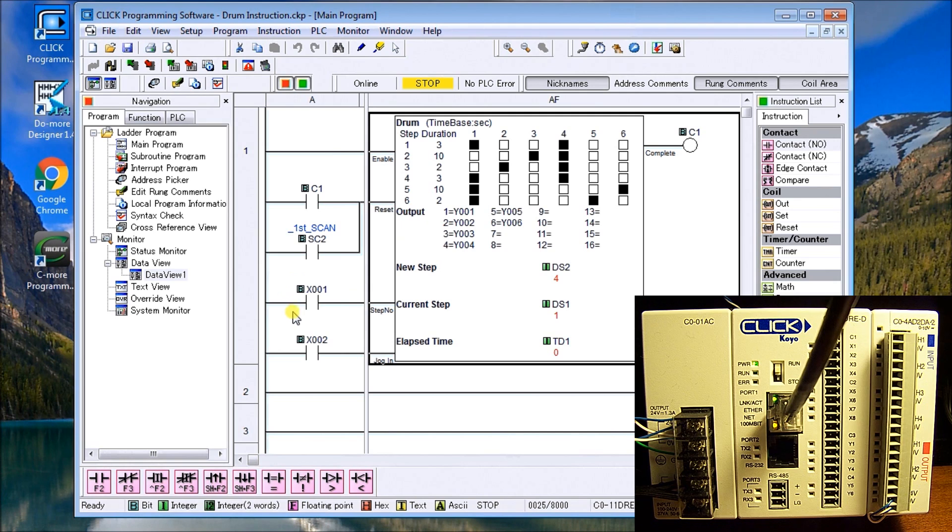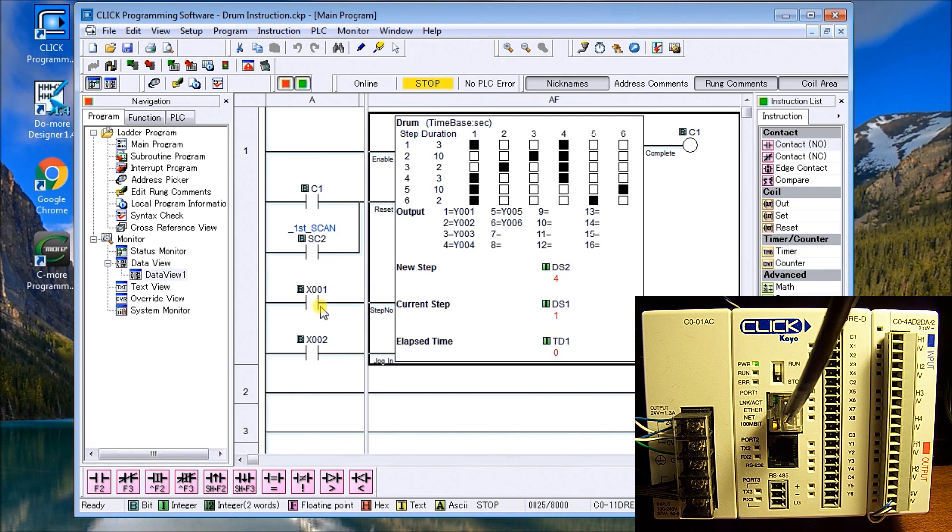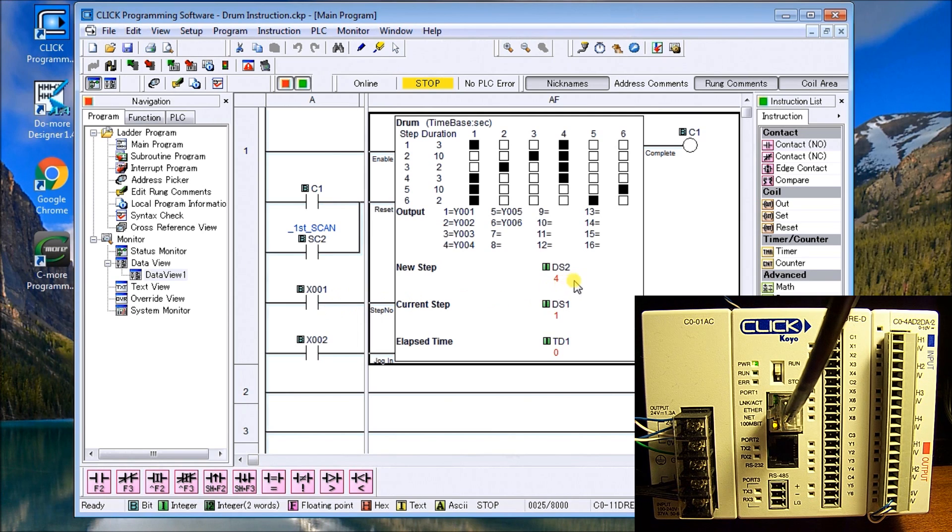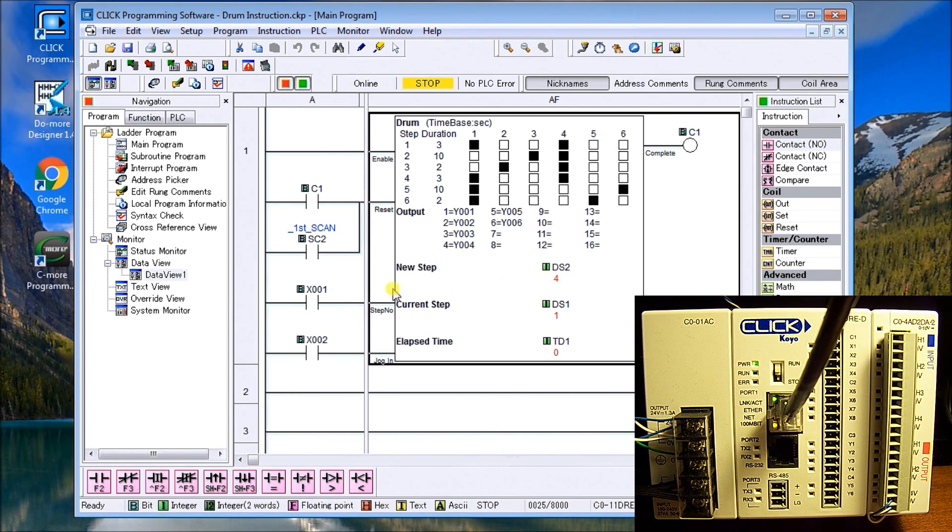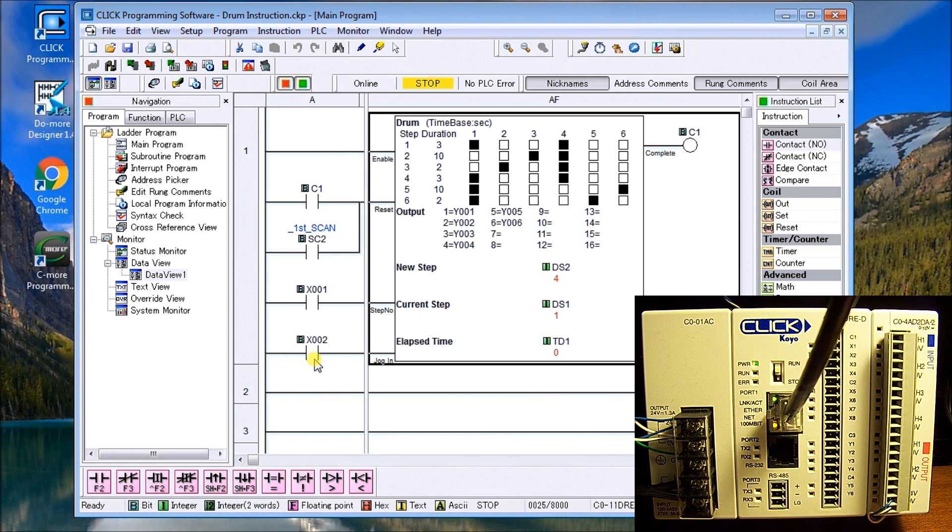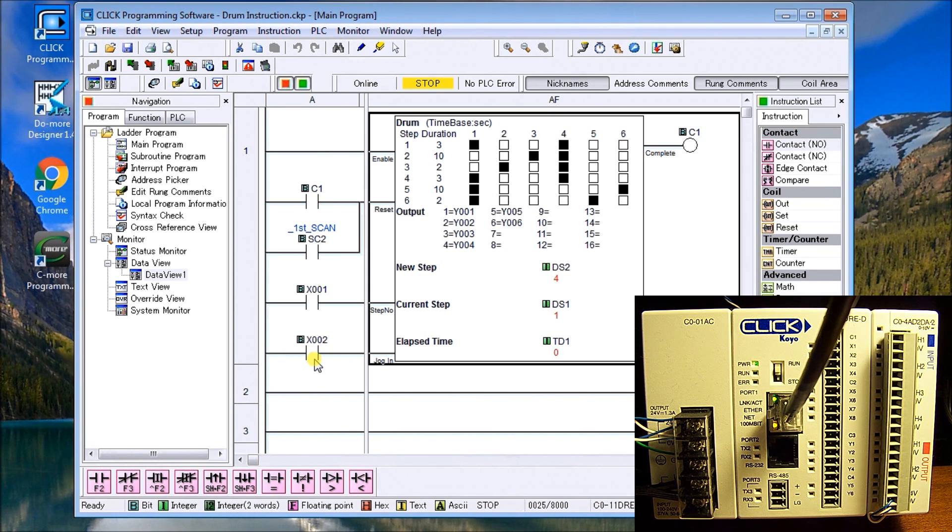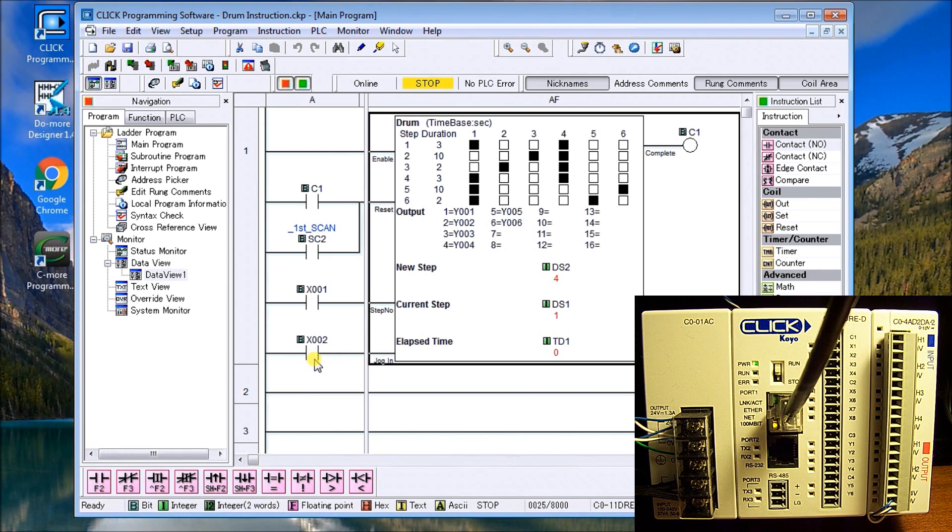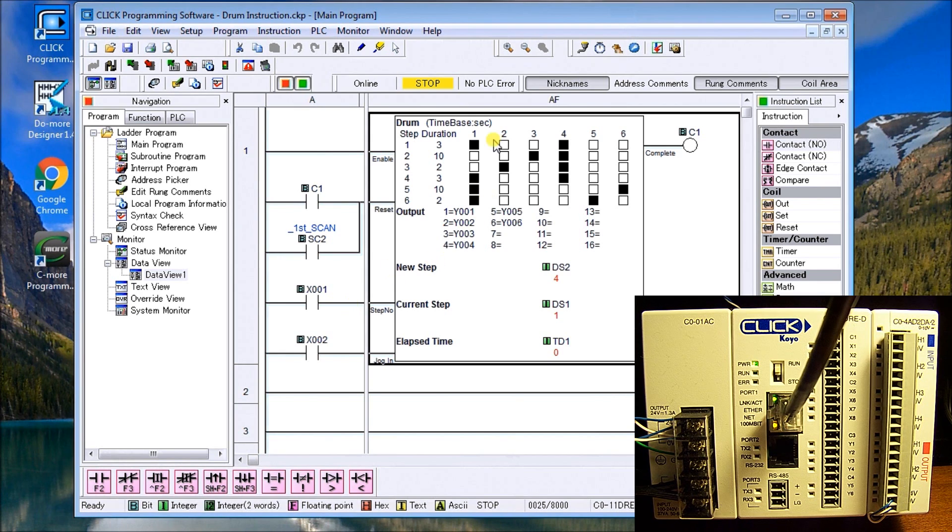We also have the step number, so X1 goes into the step number and the new step is specified in DS2 where I want to go when that input comes on. And then finally on the drum instruction we have X2 which is our jog input. That's the other input that we specified. When the jog input comes on it just moves to the next step immediately without waiting for the time.